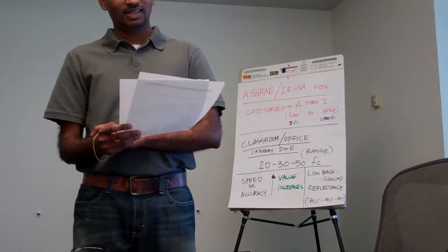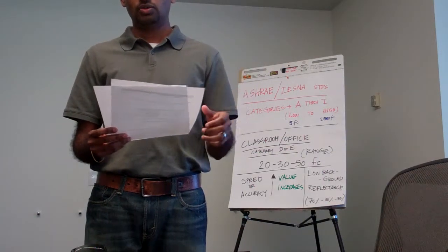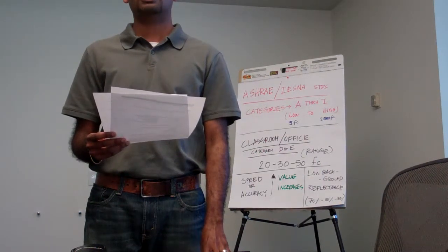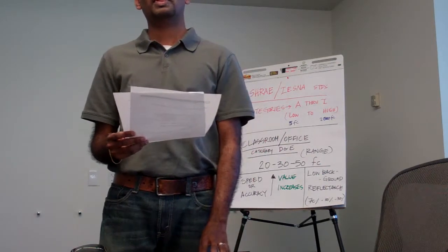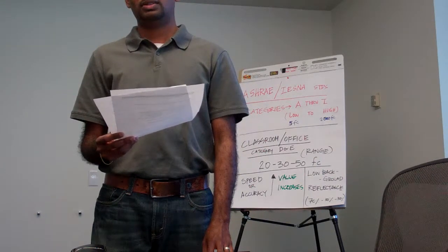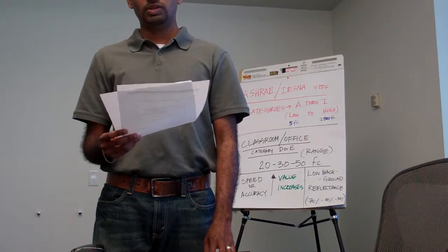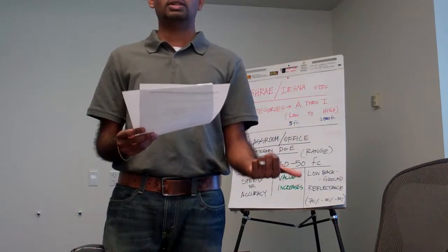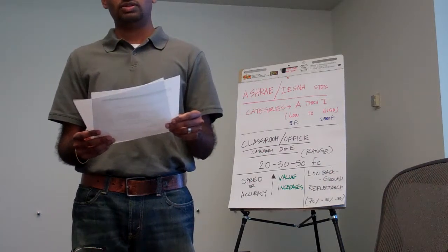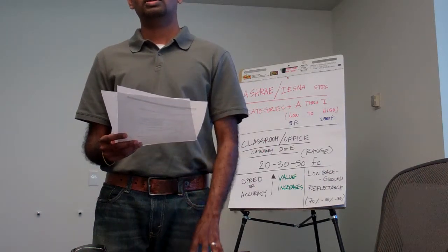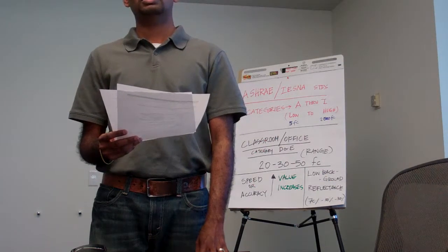If you use an all-water system, such as a 4-pipe fan coil, how would you circulate and supply fresh air? Air handlers, you could do centrally, or you could do decentralized ventilation, louvers and roof hoods. So we could do it 2 ways, either centralized or decentralized. Centralized would be to have a huge dedicated outdoor air unit, or you could have a bunch of little units in the ceiling.